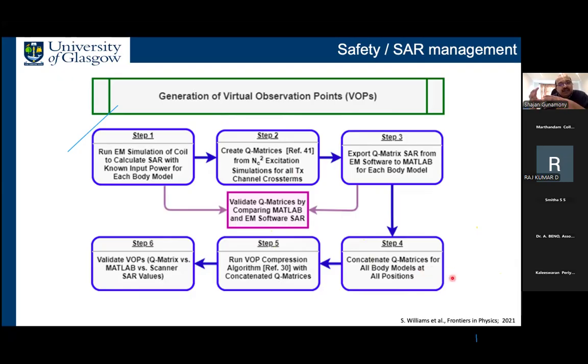This one Q matrix would be a huge file with millions of voxels, which would be too much for the scanner to handle. So there is a compression method called the VOP method, which is used to compress these millions of voxels into a few hundred data points. This file is then loaded in the scanner, and the scanner uses this information to control the power that's going to the coil.